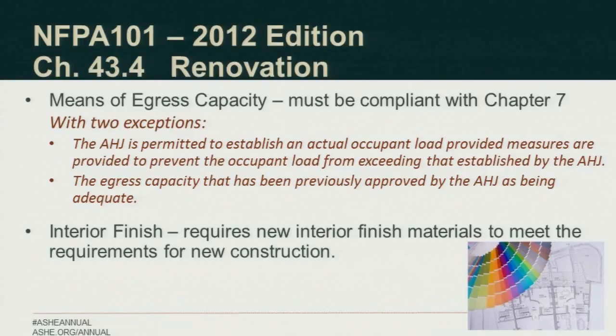Under renovation, the interior finishes are required to meet the requirement for new. So that's where your question comes in. If it's just a repair, it's one thing. If I'm replacing this whole room, now I do need to meet the requirement for interior finish for new construction. Everything else pretty much is existing, but interior finishes have to meet new.